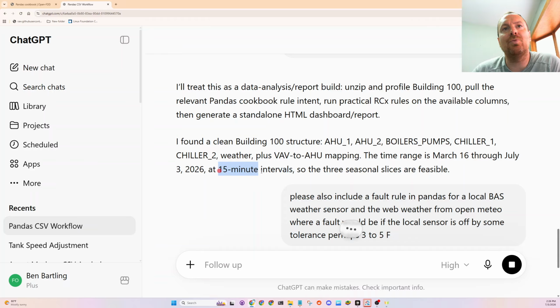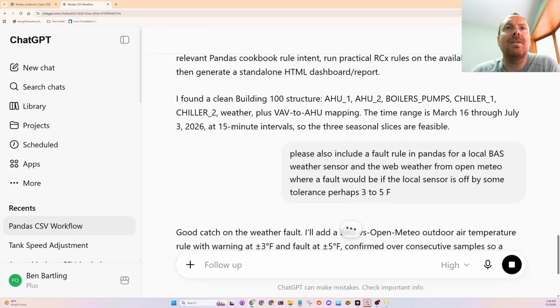Unless you're doing the internal workings of a chiller with refrigerant pressures or something, 1-minute data is very high frequency, and 5 minutes is generally the rule of thumb - you'll still get good data out of 5-minute intervals. 15 minutes, I just realized, is something we should ask to have reduced down to 5 minutes. If they have a Niagara server, which I think this building has, it's more than plenty - it can handle it.